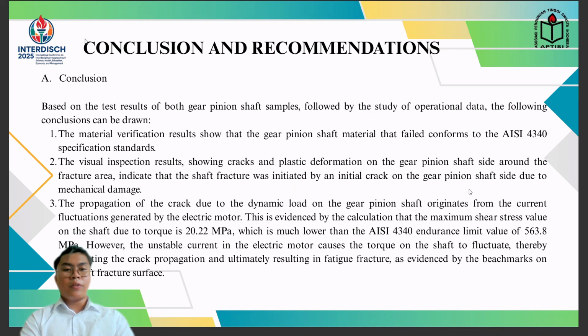One, the material verification result shows that the gear pinion shaft material conforms to the AISI 4340 specification standard. Two, visual inspection results show cracks and plastic deformation on the gear pinion shaft around the fracture area, indicating that the shaft fracture was initiated by an initial crack on the gear pinion shaft side due to mechanical damage. The propagation of the crack due to dynamic load on the gear pinion shaft originates from the current fluctuation generated by the electric motor.